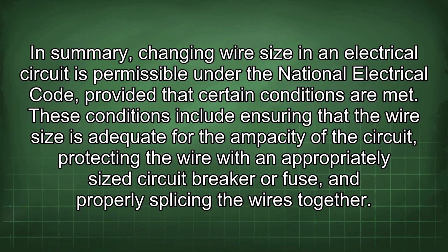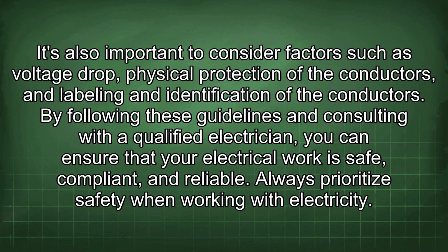In summary, changing wire size in an electrical circuit is permissible under the National Electrical Code, provided that certain conditions are met. These conditions include ensuring that the wire size is adequate for the ampacity of the circuit, protecting the wire with an appropriately sized circuit breaker or fuse, and properly splicing the wires together. It's also important to consider factors such as voltage drop, physical protection of the conductors, and labeling and identification of the conductors. By following these guidelines and consulting with a qualified electrician, you can ensure that your electrical work is safe, compliant, and reliable. Always prioritize safety when working with electricity.